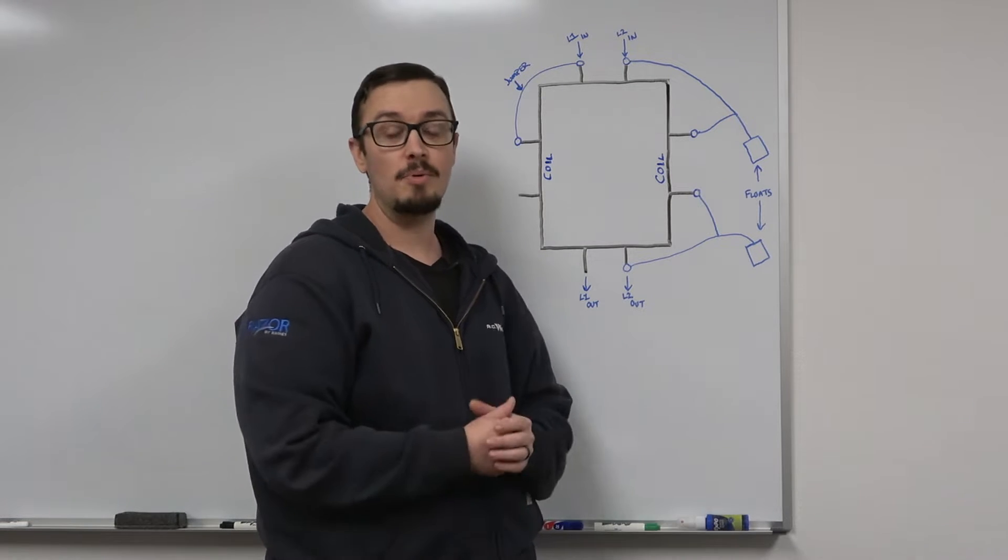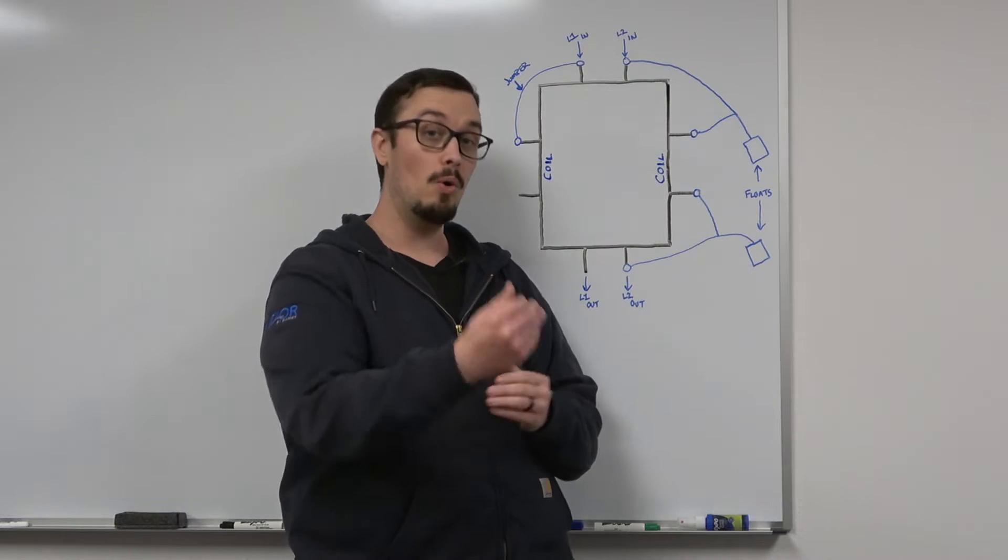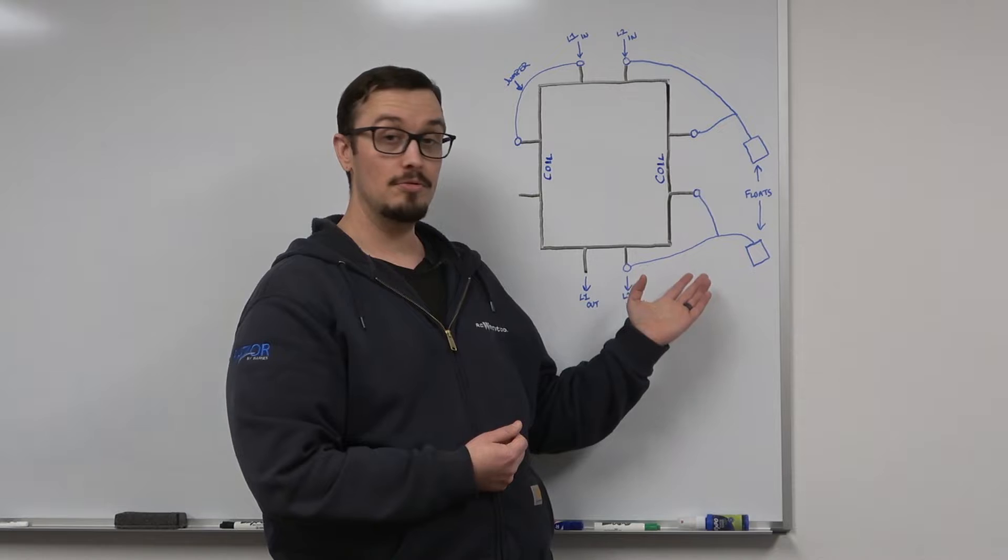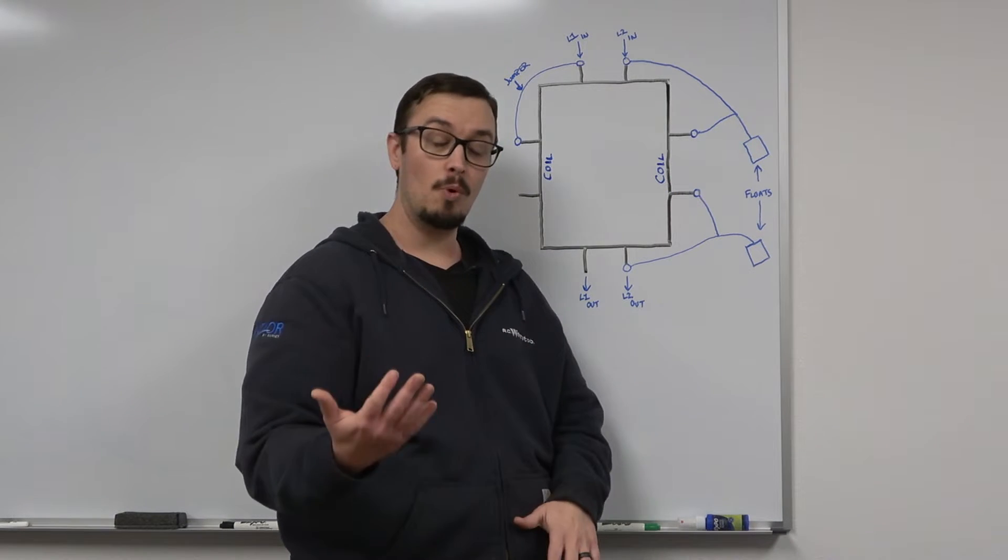This one's kind of unique because we're going to be using the relay and the float switches to create a holding circuit in the relay, which allows you to use two different float switches to accomplish a much wider range of pumping.